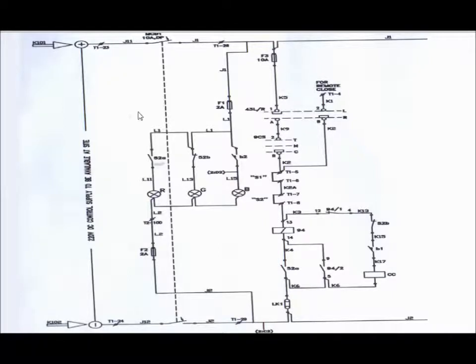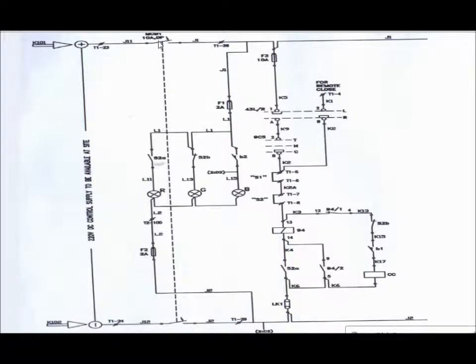Terminal numbers 23 and 24 have been allotted for DC1, that is for closing as well as for TC1, that is trip coil 1. There is one MCB of double pole type, 10 ampere rating, given in the closing path at the source end of the DC positive.